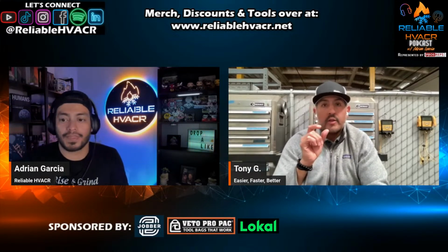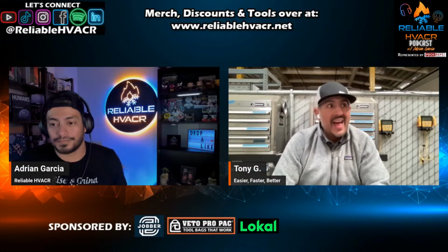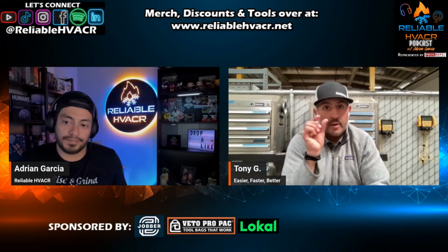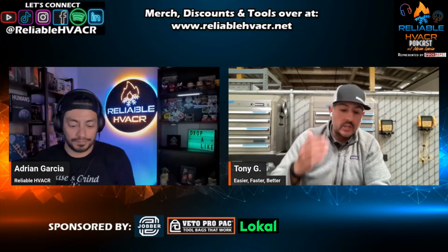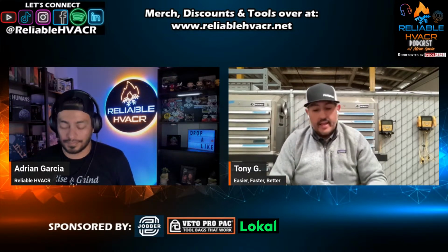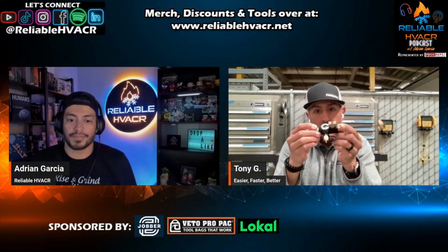we remove a big restriction to the flow, right? So the flow of refrigerant, of how fast we recover refrigerant from the system, how fast we pull a vacuum on the system, we found that if you remove the valve core, you can bring down your recovery and your evacuation times a pretty good amount. So a lot of technicians, what we do is we will have this onto the system when we recover.